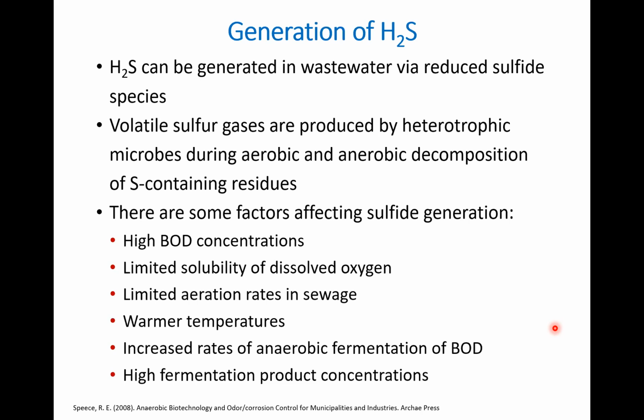And if you have a higher or warmer temperature, this actually generates more hydrogen sulfide compared with cold weather. And it can also be increased by increasing the rate of fermentation of BOD. And if you have high fermentation products, that can also be interrelated with the production of hydrogen sulfide.